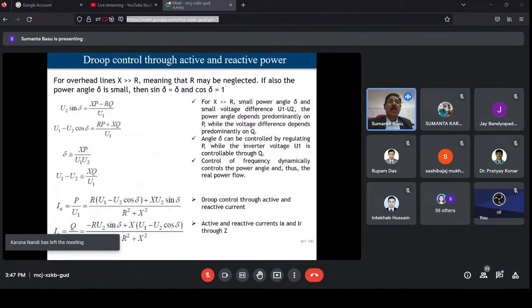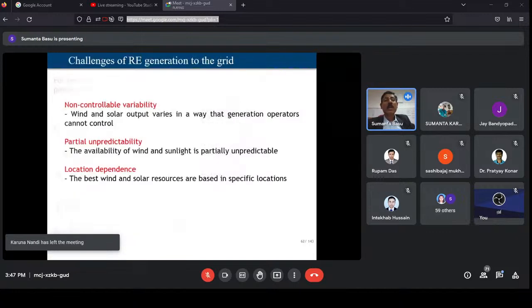All of you know how these methodologies work. As I told, normally in all such cases we use the voltage source inverter. We can implement the droop control through active or reactive current, or we may control active power through the power angle and reactive power by the voltage. Both methodologies are available in the market, but as I told, it is very limited for large scale inverters, meaning the higher rating in utility scale. The implementation of the various methodologies is still yet to be done.